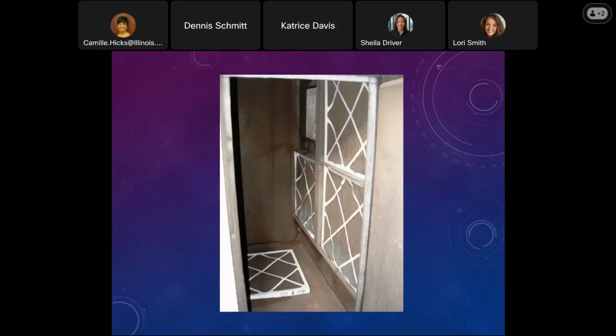This was actually in a hospital in Illinois. They wondered why they haven't replaced their filters for a while, because their flow rates across the filters were all reading good because the filter is not in place. So it's just allowing free air from the exterior directly down line into patient care areas. So this is absolutely a violation. Fortunately, this was not for a surgical unit because they have their own HVAC and mechanical requirements, but this was for a med-surg unit.